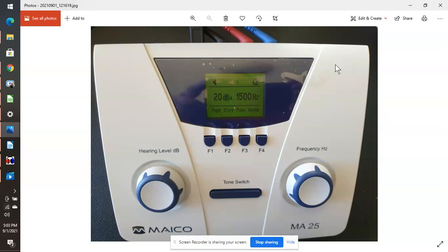The other thing with this audiometer, it has multiple methods of powering it up. You can either use the external plug pack, which is supplied with the audiometer, and that'll run it off there. If it's plugged into a computer, so that this USB cable plugs into a USB port on a PC, the PC will usually have enough power to power this audiometer. So you don't need an external power supply. It'll actually draw the power from the computer. And if you're not doing that, you can have internal batteries inside there. It takes, I think, 3 or 4 AA batteries. There's a flap on the back, a little cover, you just flick it open and you'll see where the batteries go, and you can run it on battery power if you're going out into the field, so you don't have to worry about getting power for it.